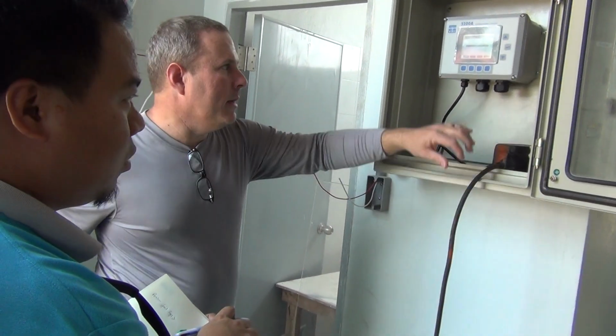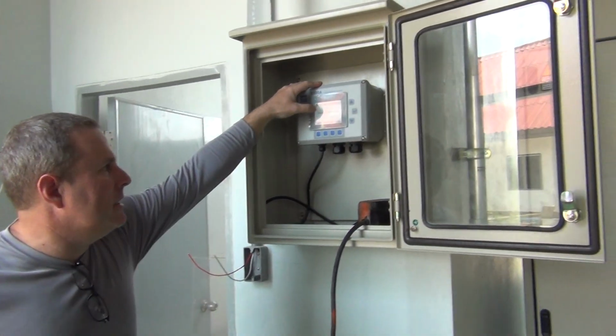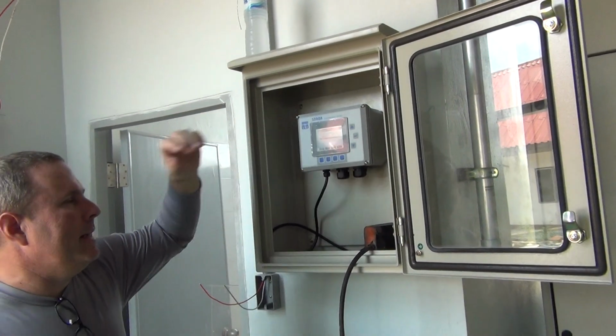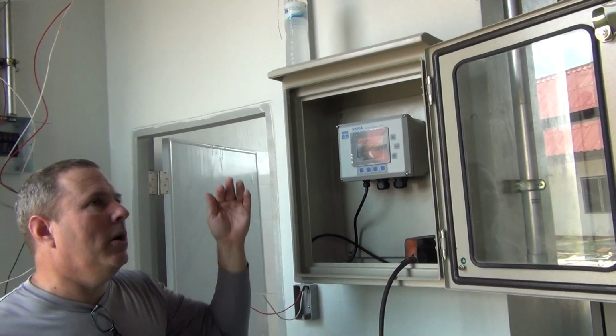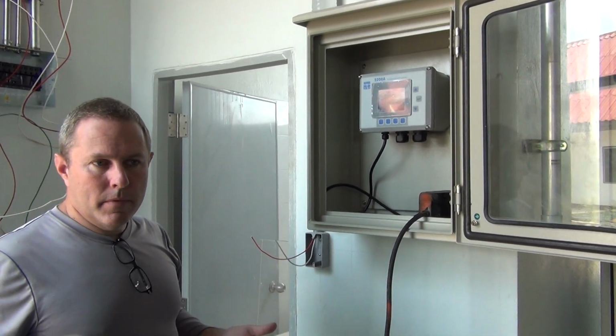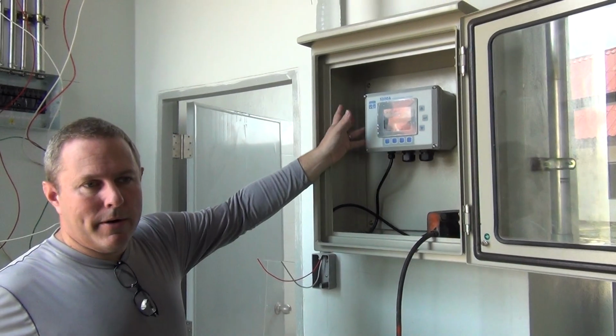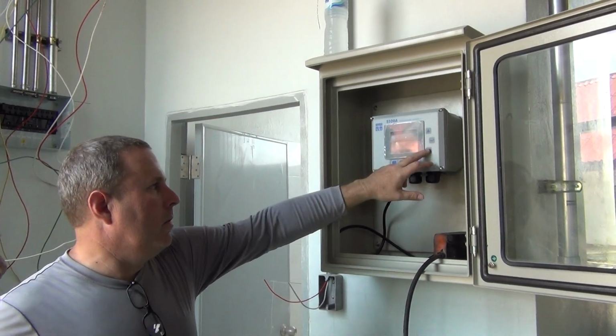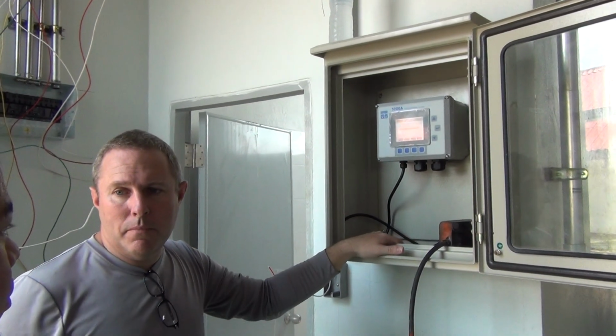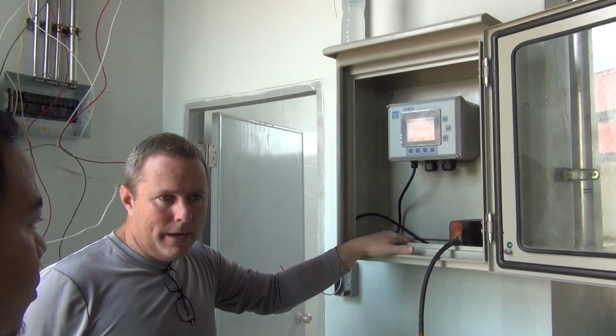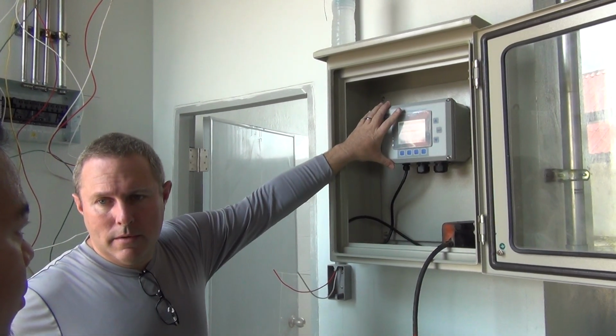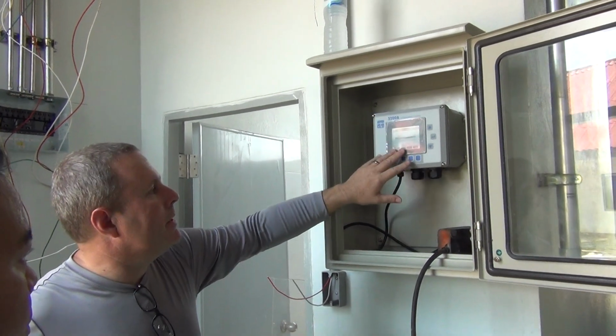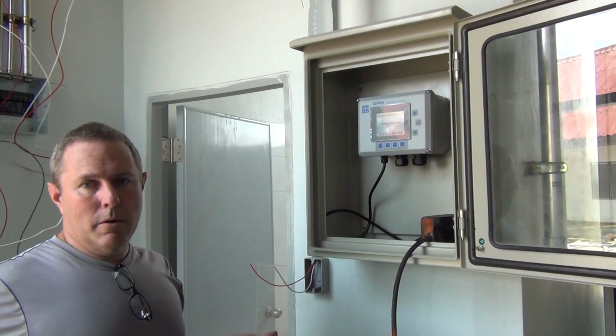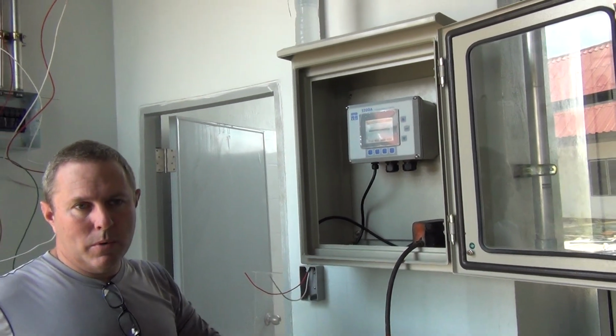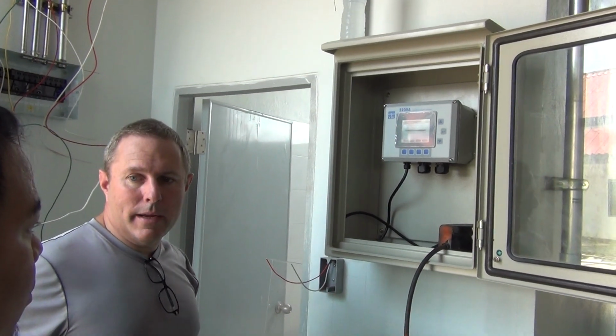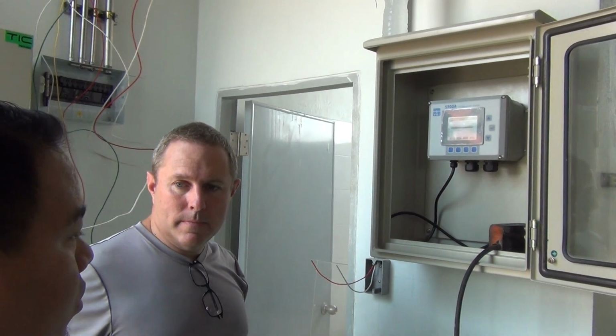230 volt. Yes. Okay, so what you may choose is, for example, that if the AC power were to fall below 180, then it could switch to battery backup. So if you do that, you need a 12 volt power source, like a battery, that you would wire in where I showed you. And then we would set this up with the low battery alarm and the cutover, where if the voltage drops, it switches to the battery. Does this make sense?